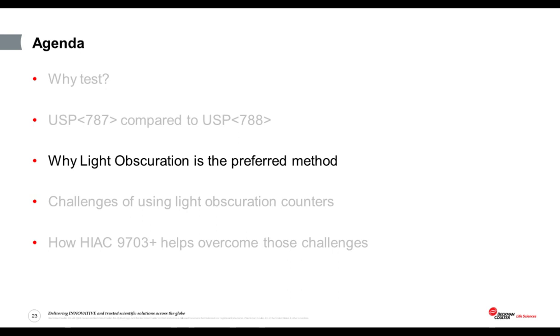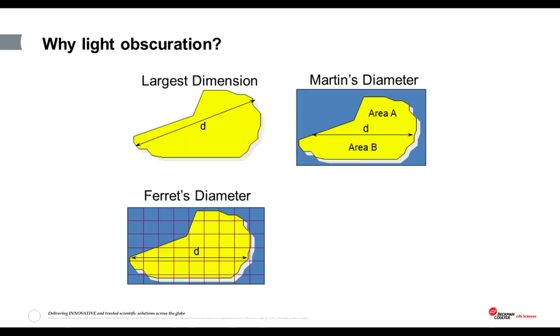So I mentioned several times there that light obscuration is the preferred test in both USP 788 and 787. And now I'll explain why that is. The problem was that particles contaminating our products are rarely conveniently spherical in nature. So how do you size them and compare them between batches when particles are so irregular in shape and you're counting them by eye, which was the previous method? There are several sizing conventions, but which is correct? And on top of that, sizing them by eye using a microscope is a very subjective process. And what we find is that technician differences in methods creep in, and as does human error.